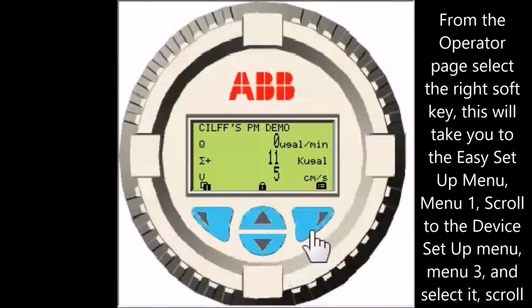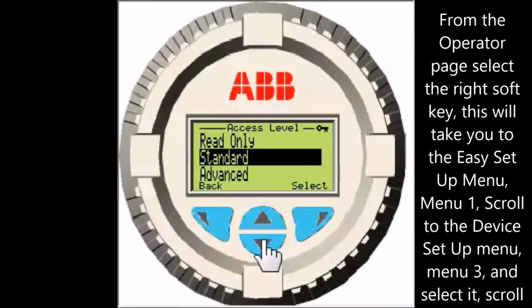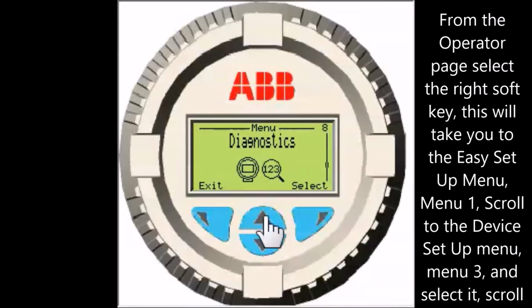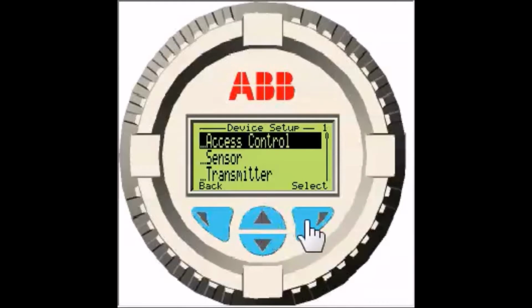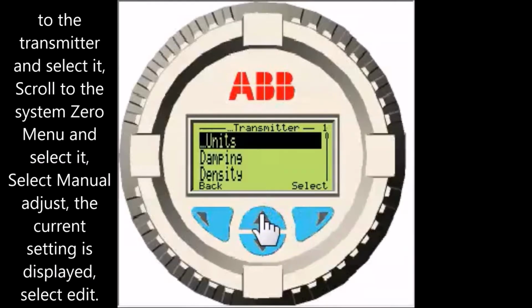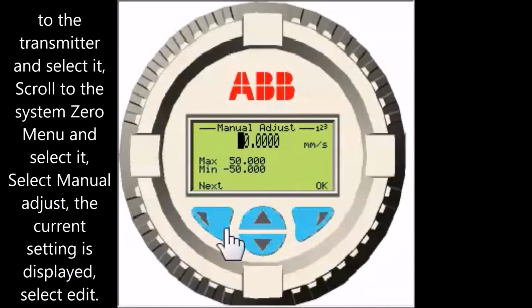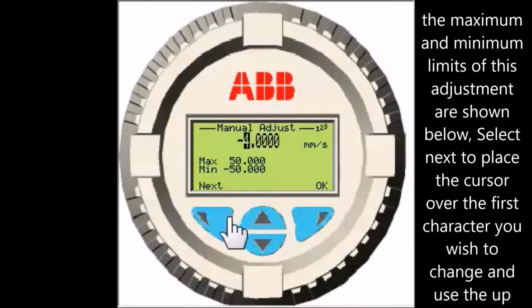From the operator page, select the right soft key. This will take you to the Easy Setup menu, Menu 1, scroll to the Device Setup menu, Menu 3, and select it, scroll to the Transmitter and select it, scroll to the System Zero menu and select it, select Manual Adjust. The current setting is displayed, select Edit.